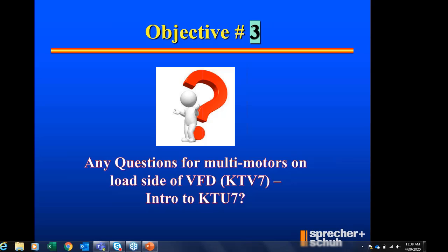Okay, another question: a KTU7 doesn't require a convenience contactor for signaling when you have an auxiliary contact, correct, or auxiliary accessory? I guess the answer to that would be yes. You only use the contactor if you want to remotely operate the device from a remote push button or whatever. If you're doing it manually, KTU7 does have the ability to put an aux contact in there that will follow the trip or follow the operation of the contactor on or off. Roger that. Totally good answer, and you summed it up in saying that the contactor is merely a means of energizing or de-energizing from a signal as opposed to manually operating the device. Yeah, auxiliary and trip contacts exist on that KTU7 as an offering.